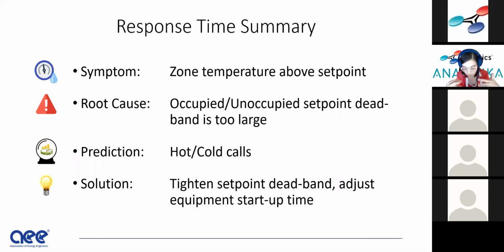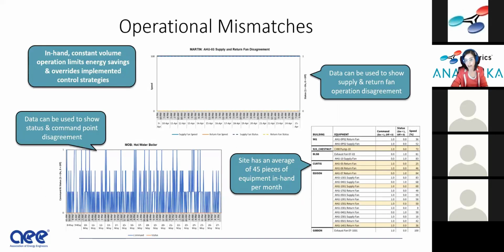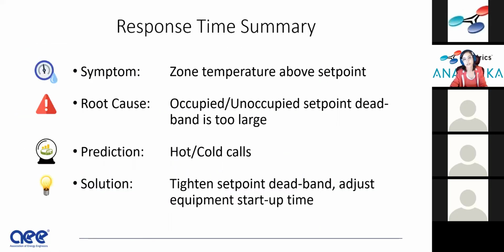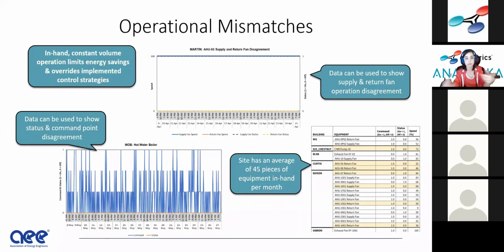They might change the occupied set points a bunch of times and try to figure that out, without seeing that response time and fine-tuning the deadband. So here we had to fine-tune the deadband. But knowing the response time is powerful because you can better schedule equipment by having that information. And that's some of the asset performance over time that I'm talking about. Understanding how all this is related and how long it takes for zones to get up to temperature, right? That's all dependent on the space volume, the people in the space. Pretty complex problem that we can help solve.